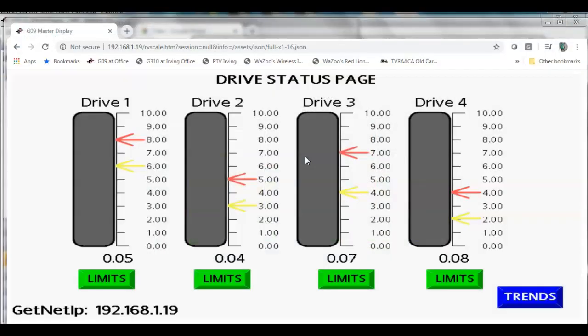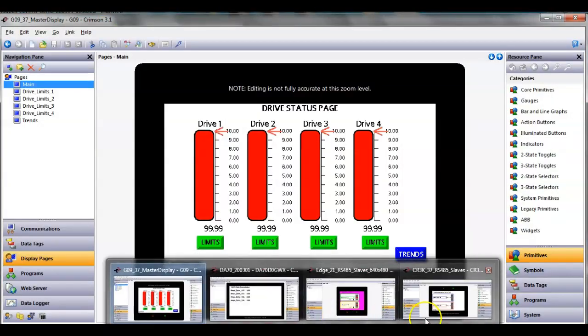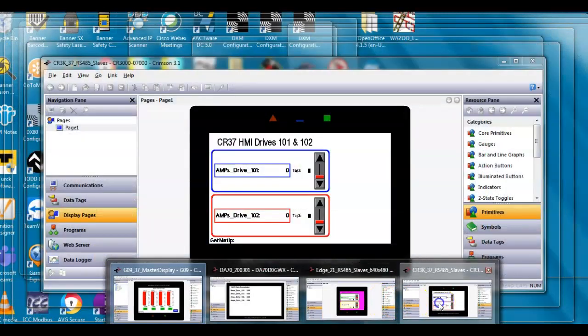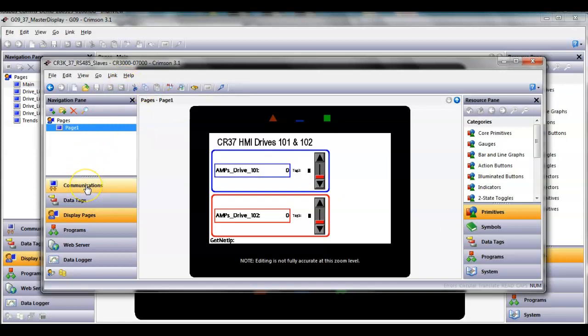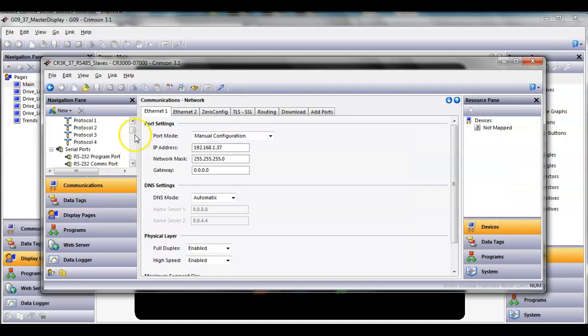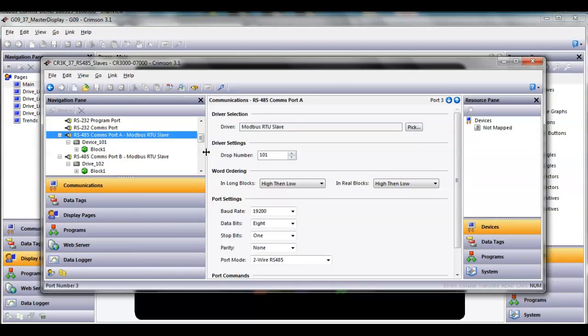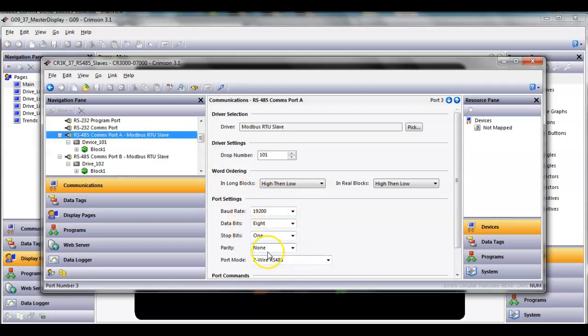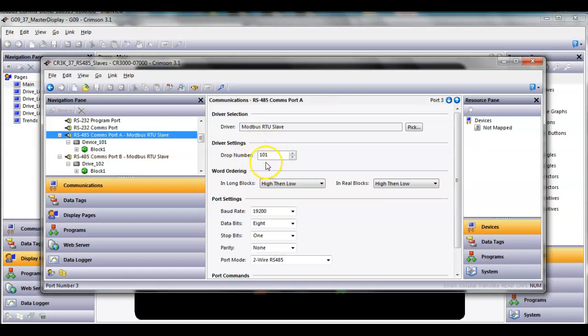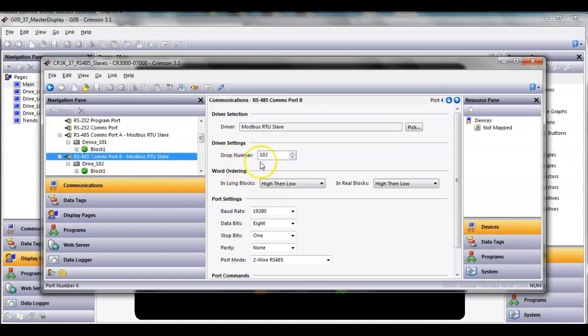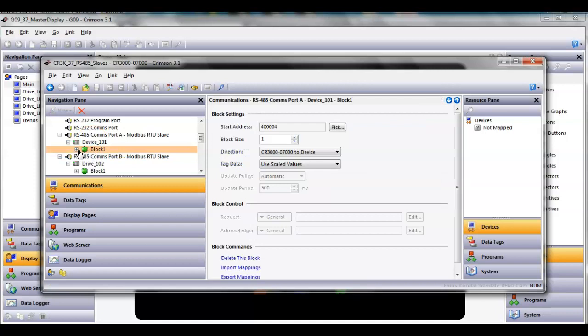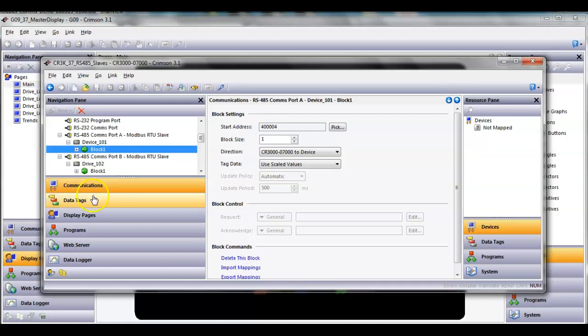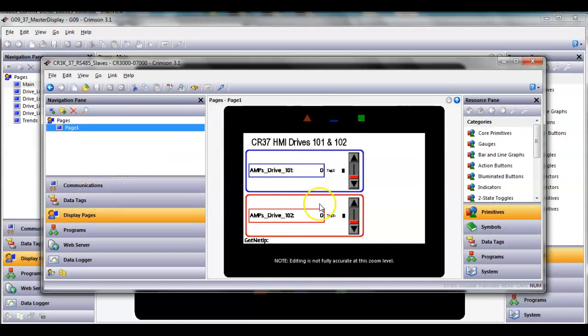Let's start off talking about our different slaves out there that are going to act as Modbus drives. Here I have the CR-3000 screen. In communications, I've got this set up as a Modbus slave. This is drive 101, so I got the device set to 101. If I go down to this other port, there's device 102. Since these are slave devices, I'm going to mimic the amps drive, the amperage usage of these drives through this program.